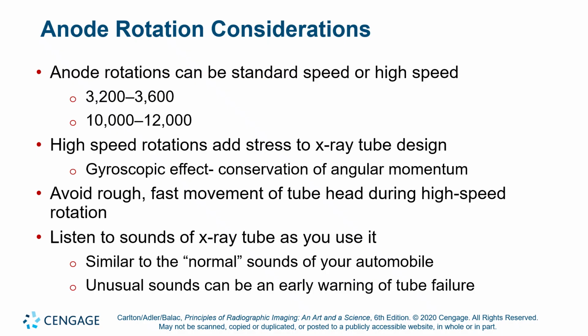All right, so your X-ray tube should whine a little bit, more like your vacuum cleaner. Your vacuum cleaner has a whining sound to it, kind of sounds like a jet turbine. That's the motor of your vacuum cleaner. When the rotor bearings start warping, then you get this gravelly crunching sound laced in with the whine. So any unusual sounds, if it doesn't sound like a constant tone whine, kind of like a whir sound, if there's any variance to that, or if there's any gravelly sound, that might be the rotor and the stator are about to fail. The stator is either about to burn up or the rotor bearings are warped. Those are the two most common errors with the induction motor.